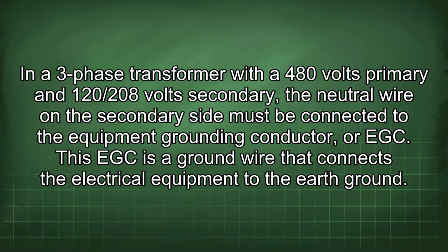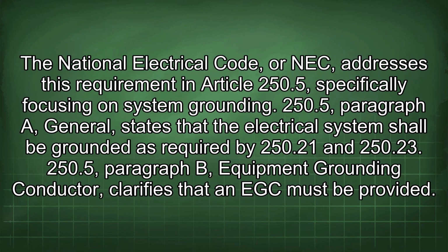In a three-phase transformer with a 480 volts primary and 120/208 volts secondary, the neutral wire on the secondary side must be connected to the equipment grounding conductor, or EGC. This EGC is a ground wire that connects the electrical equipment to the earth ground. The National Electrical Code, or NEC, addresses this requirement in Article 250.5, specifically focusing on system grounding.